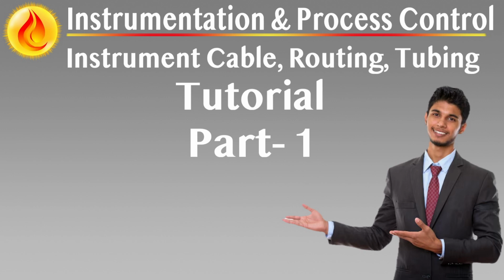Current and voltage considerations. For 0.8 millimeter diameter conductors, approx 0.5 millimeter squared, the continuous current rating is 1 A per core with a fuse limit of 4 A. Voltage drop must be calculated for each loop to verify that instrument terminals receive sufficient supply. Where the drop exceeds permissible values, larger conductor diameters or adjusted power supplies must be selected.